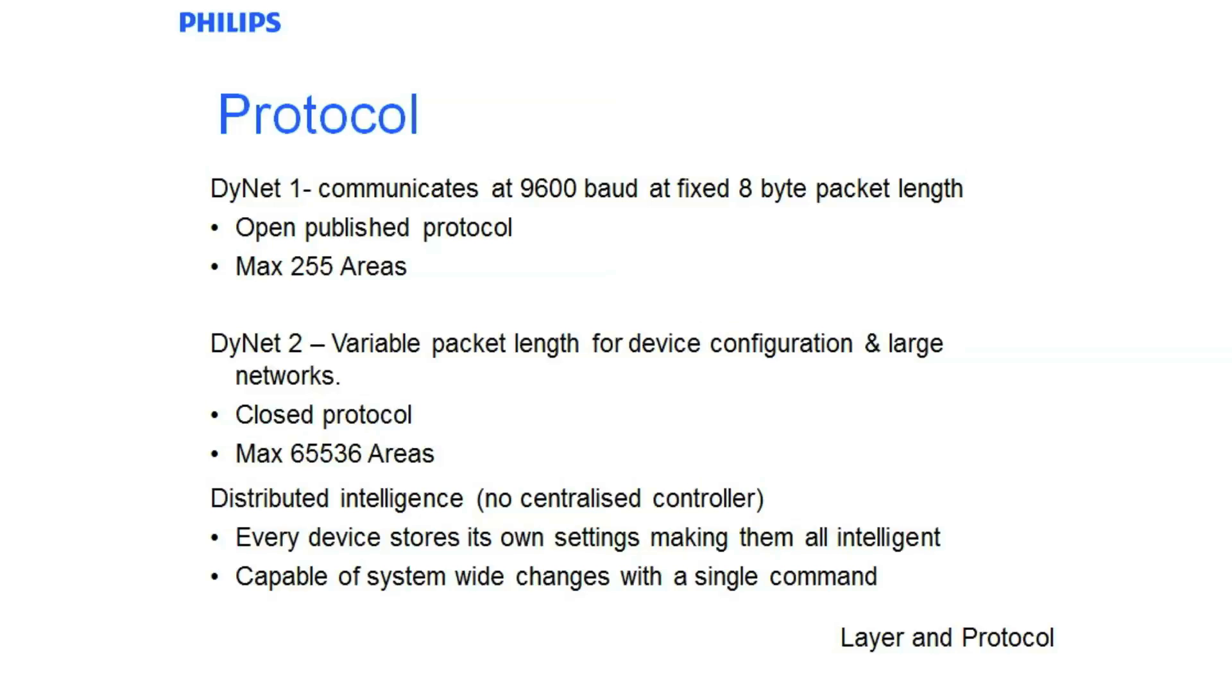DyNet 1 has been around for over 20 years. It communicates at 9600 baud and has a fixed 8 byte packet length. Typically these are the messages that are put out by any field control panels or any sensors. It's an open, published protocol. Limitations are that there are a maximum of 255 areas and within each of those 255 areas there is a maximum of 255 channels. Although this may not sound like a whole lot, this is a huge number and we have been able to control many large museum spaces and large office buildings within the confines of that.